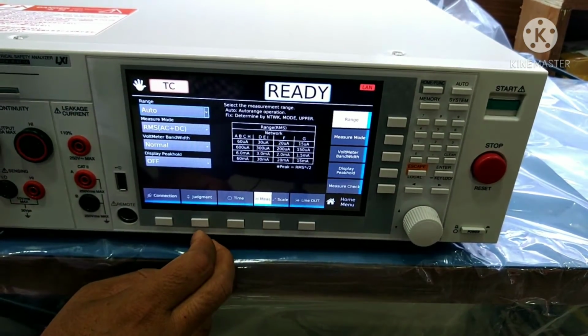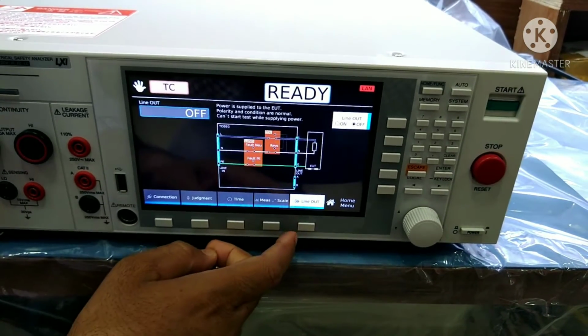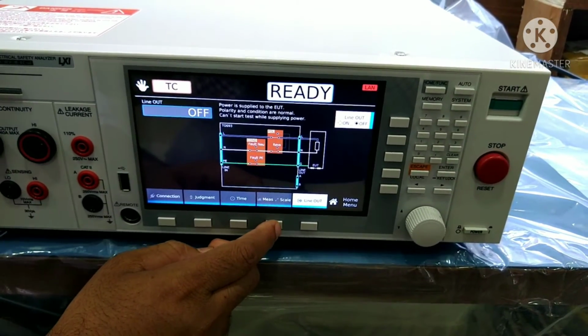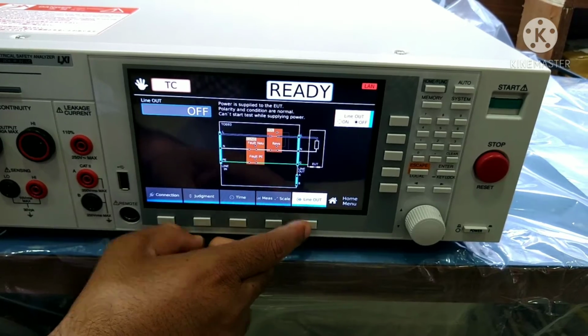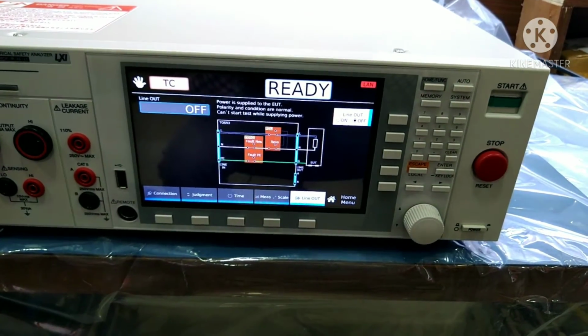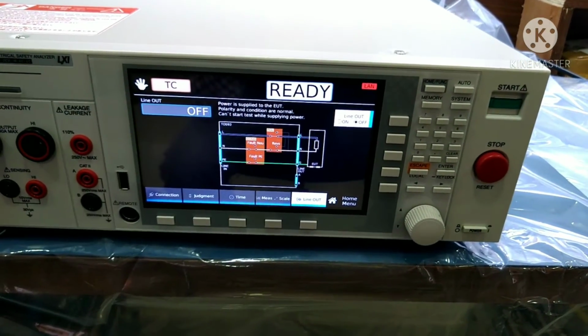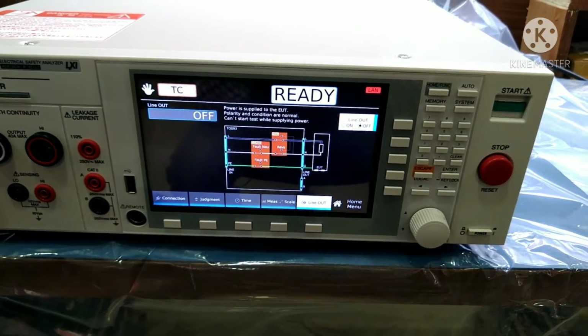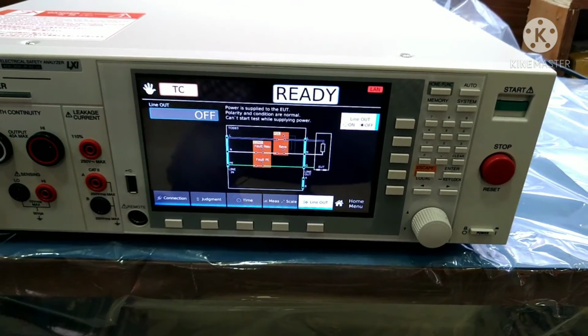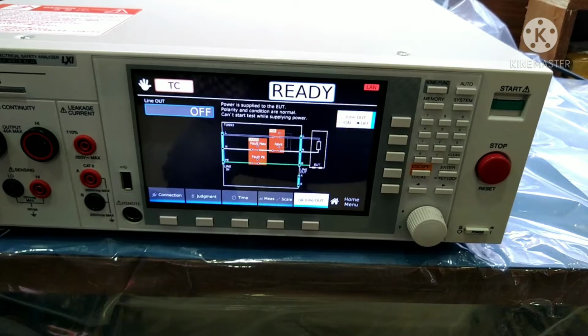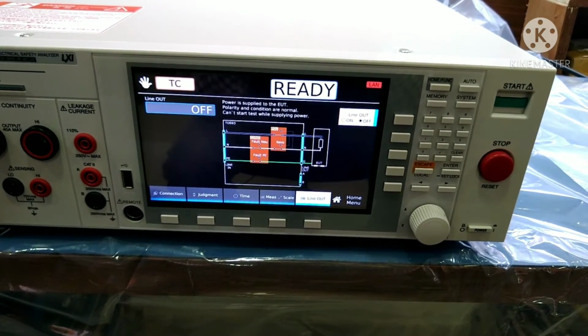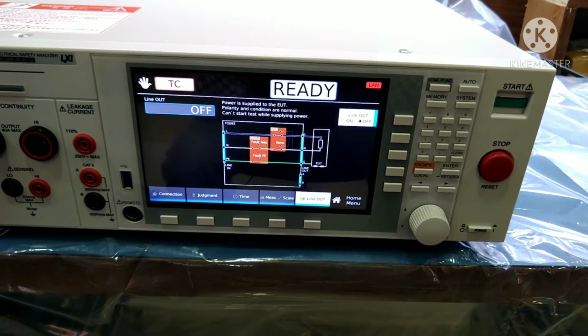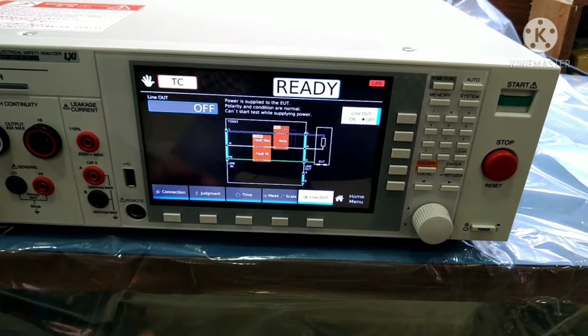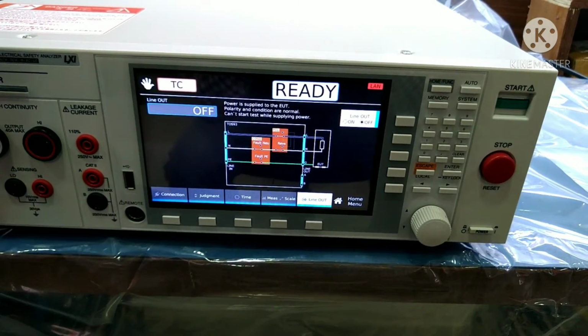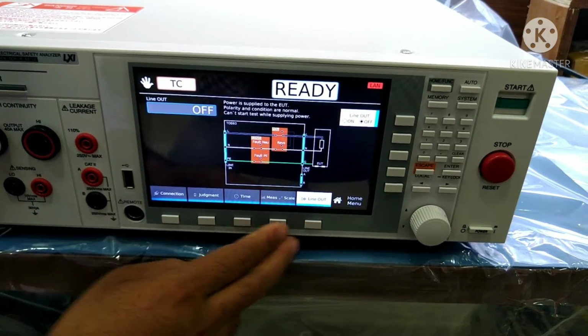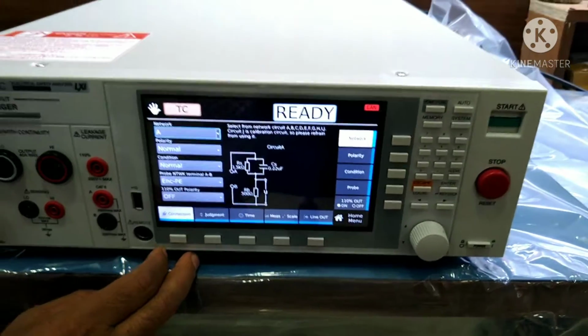This is a measurement scale. This is a line out. Line out means during the test time, it will generate the set voltage. Like if you have a line voltage of 230, it will generate 230 volts to your devices, like any device, refrigerator, washing machine, whatever you want to check the test voltage. Sorry, touch current. So we are going to start the test.